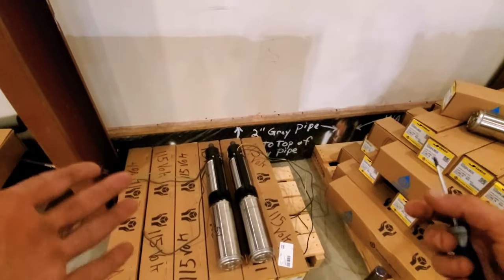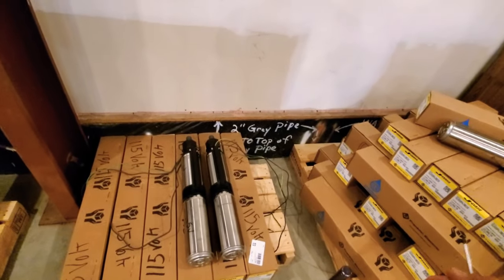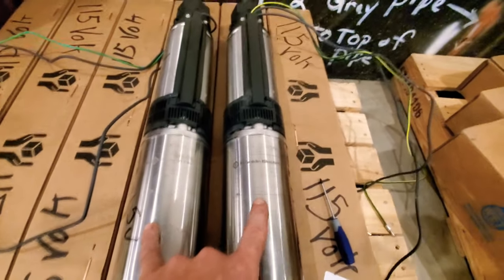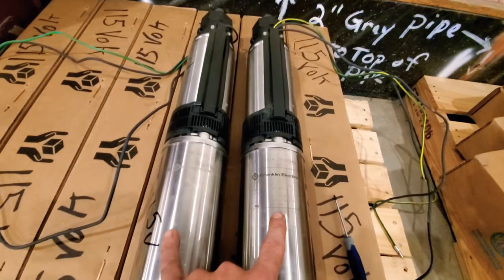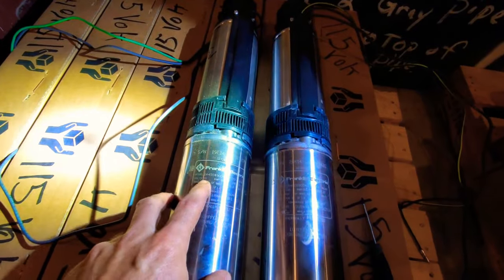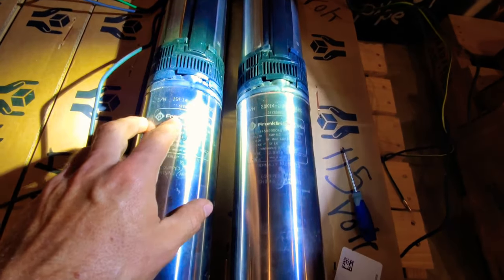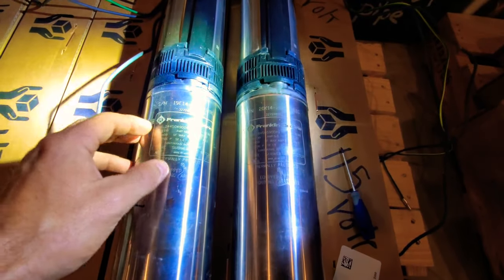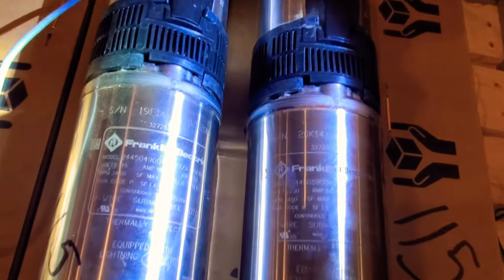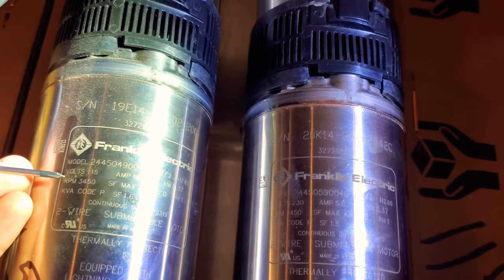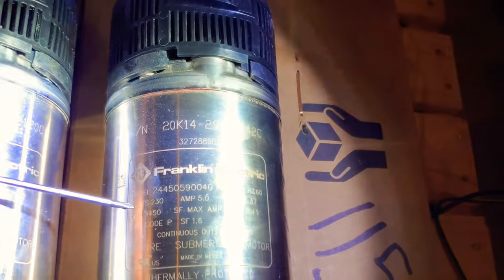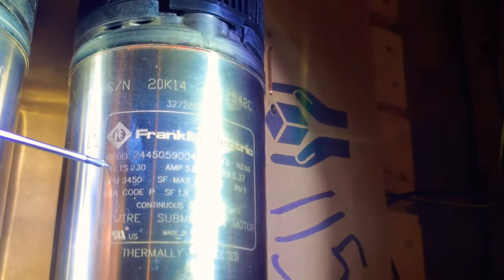So how do you tell if you have a 115 volt system or 230 volt system? If you come to the pumps, this is the only way you can do it if you have the ability to see the old pump. On any pump you're going to have your inspection tag right here with all the information on it. If you find right here, we have volts 115, and we come over here to this pump, it says volts 230.